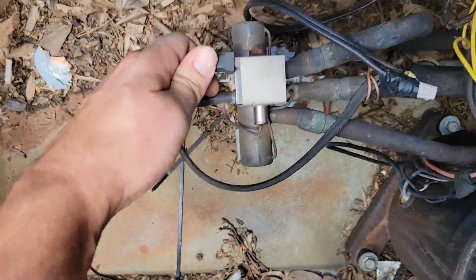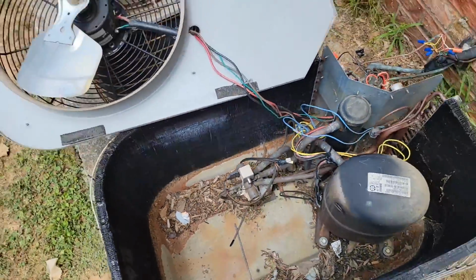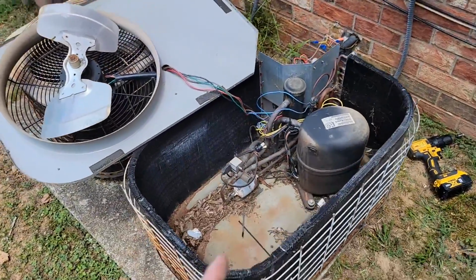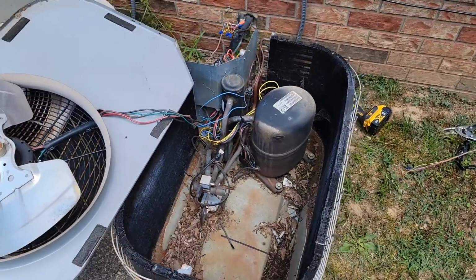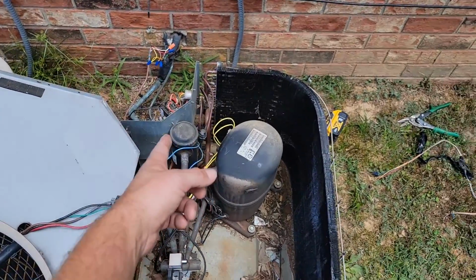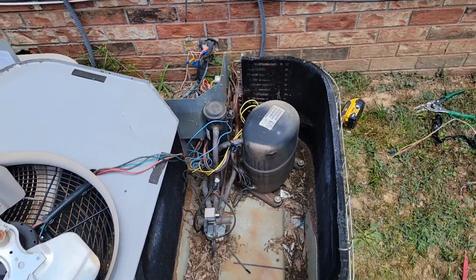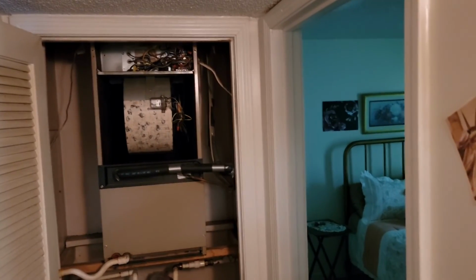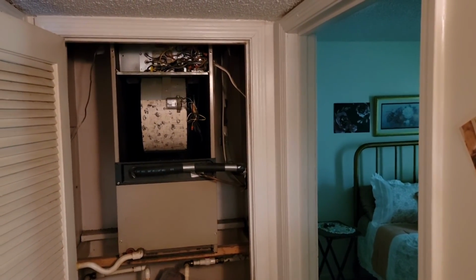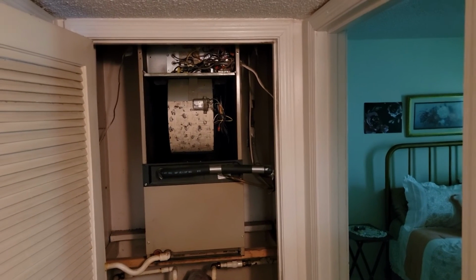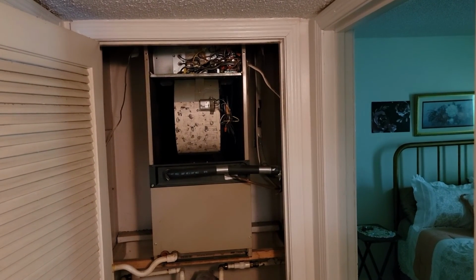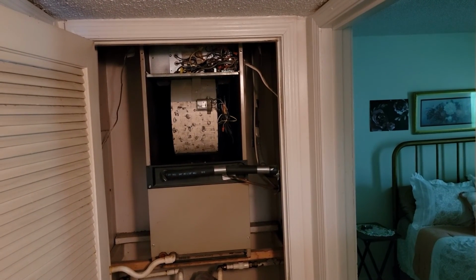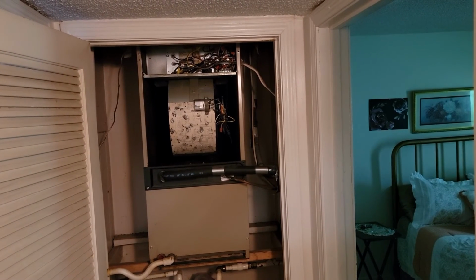Put this back on, go back inside, turn the breaker back on. Let's see if it blows. If it does, it was the reversing valve coil. If it doesn't, I'm gonna put that wire on, turn it back on. It's the contactor coil. Let's go. Contactor coil is the only thing isolated right now. So if this fuse blows, then it's the reversing valve coil. And if it doesn't, then we know it's the contactor coil.